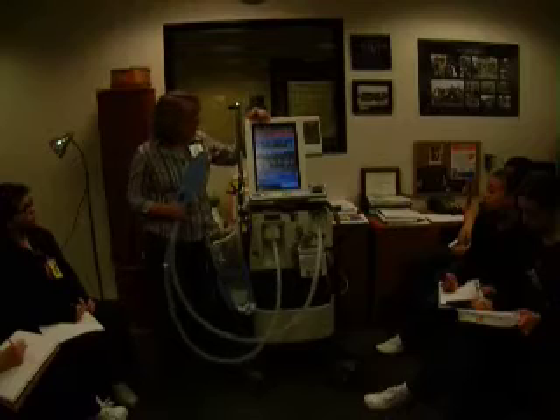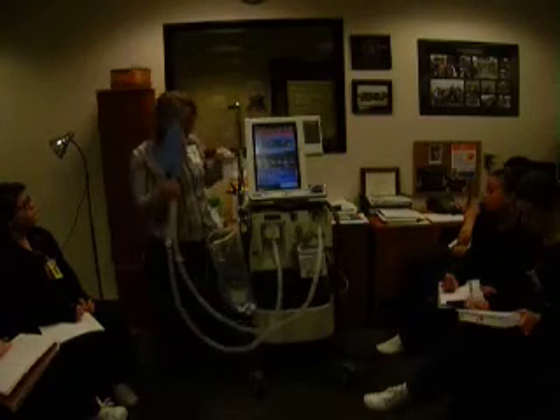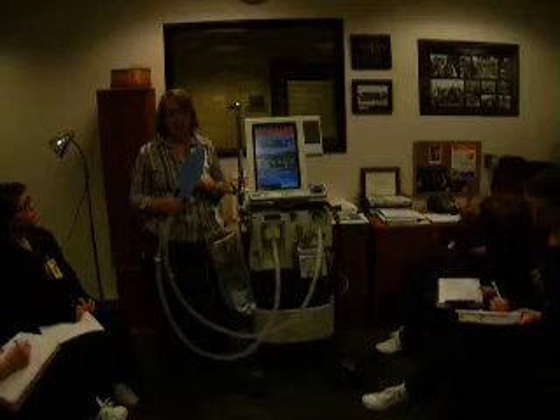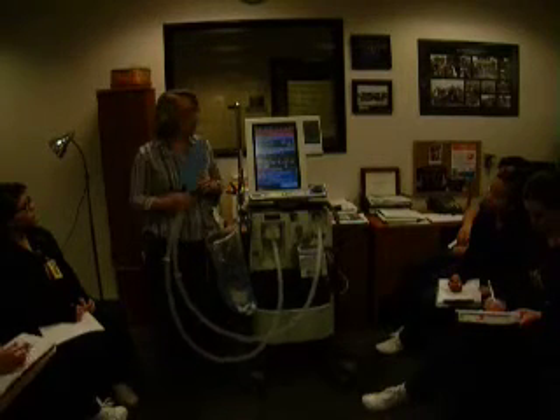See, it will give you a procedure error. What it thinks you did is it thinks you hooked the ventilator up to the patient without setting anything. Because we haven't set any settings, we haven't done anything except turn it on. So the ventilator's going, why did you do that? So that's a procedure error. It's not going to let you finish until you unhook.